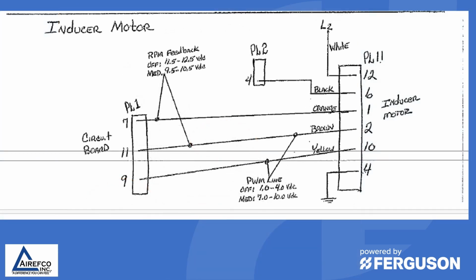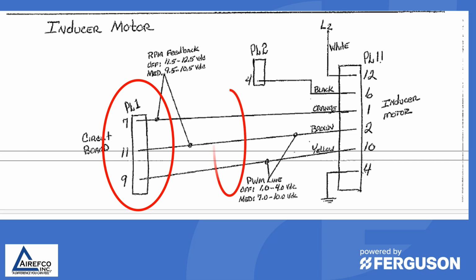So when you're checking these voltages, you want to make sure that you double check at the board itself to make sure that the board is putting out the correct voltage as outlined in the troubleshooting guide. You want to also make sure that the voltages are getting through the harness. Many times the harness is the problem. There's a broken wire or a pin that is not making connection through the connector pins in the harness. And then you want to check at the pin on the motor itself to see if the voltages are getting to the motor through the harness. If they are, and the motor's still not running, then that means that you have a bad motor.